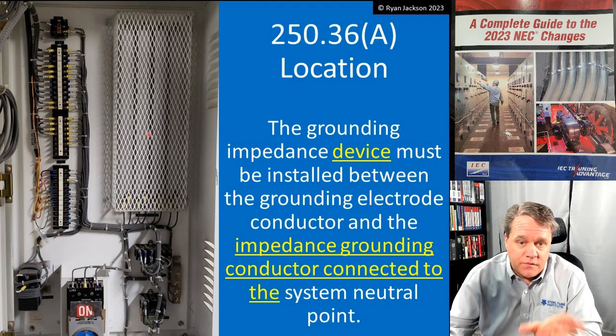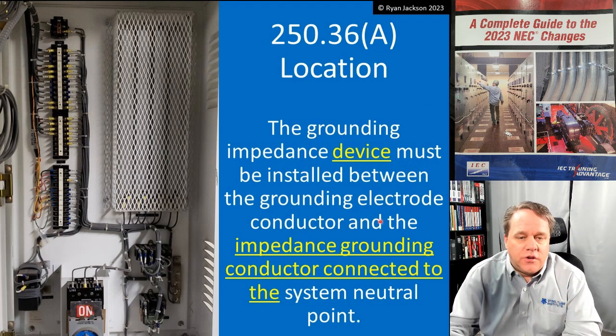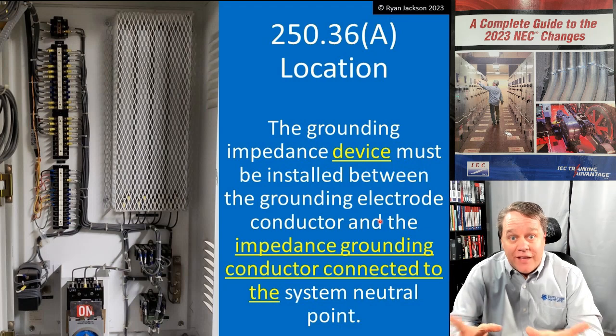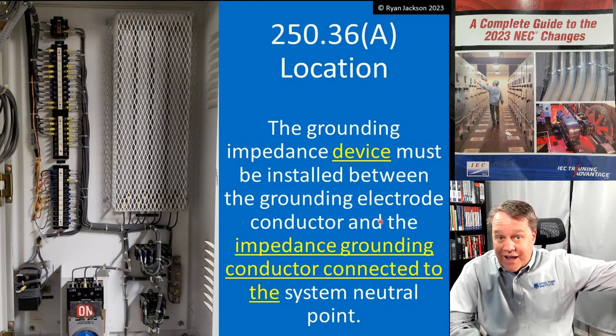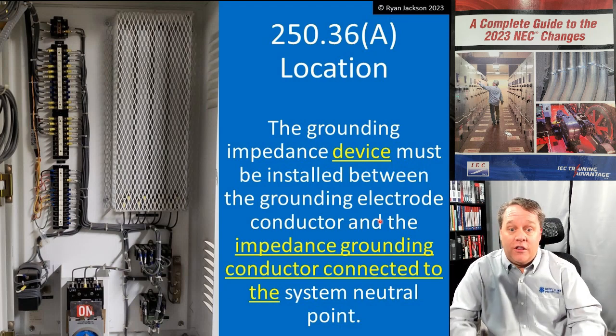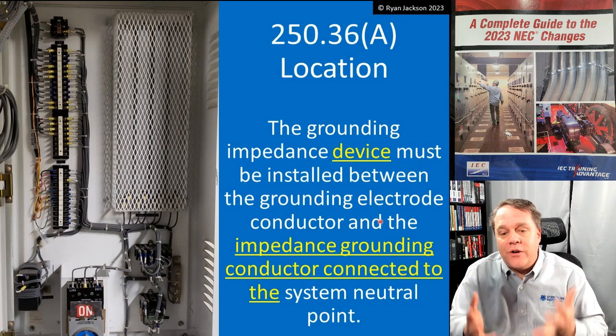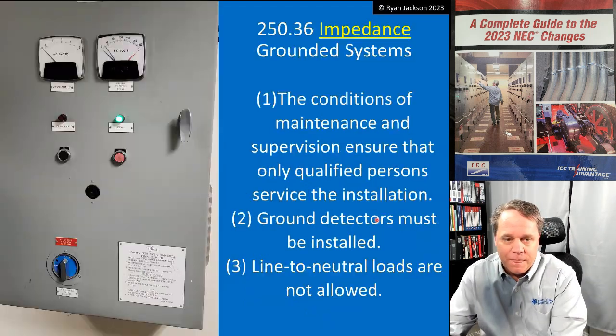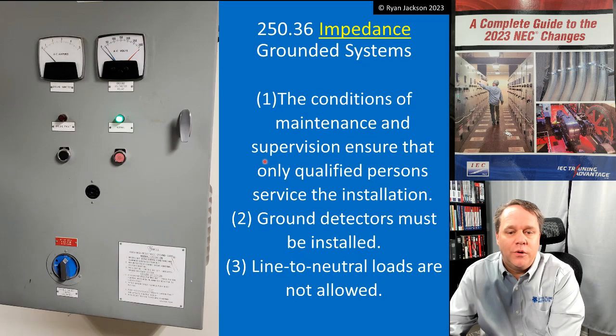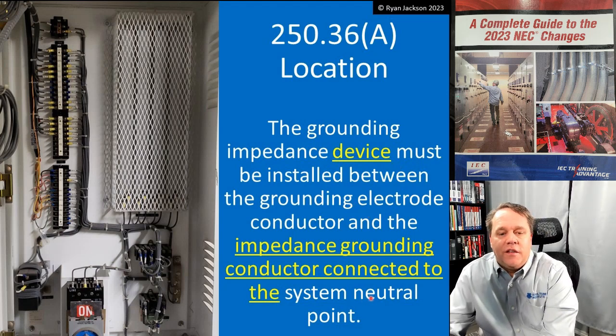Section 250.36(a) says the grounding impedance device - the actual impedance - must be installed between the grounding electrode conductor and the impedance grounding conductor that's connected to the system neutral point. That wire didn't used to have a name - we used to call it a neutral before 2008. That's when I got in touch with Chuck and said we have to fix this. Then Eric came along and said, 'Let's call it the impedance grounding conductor.' So this conductor is the impedance grounding conductor.